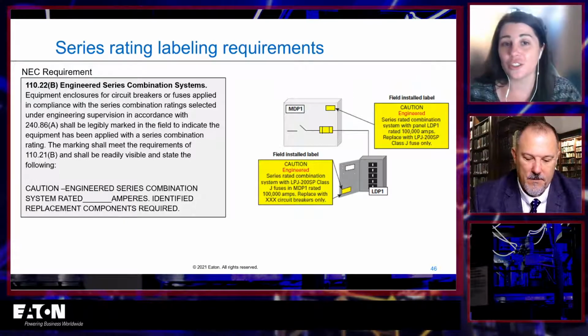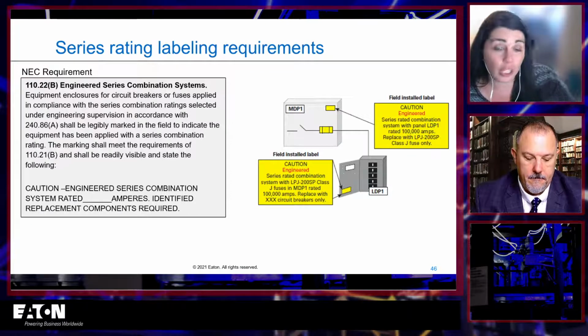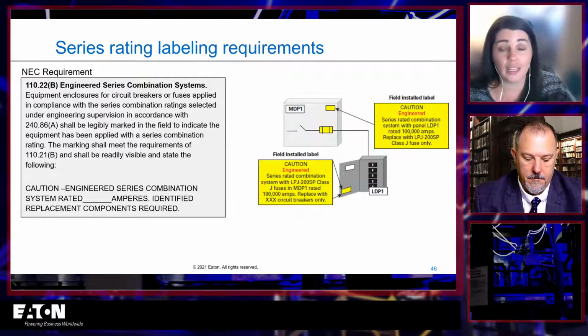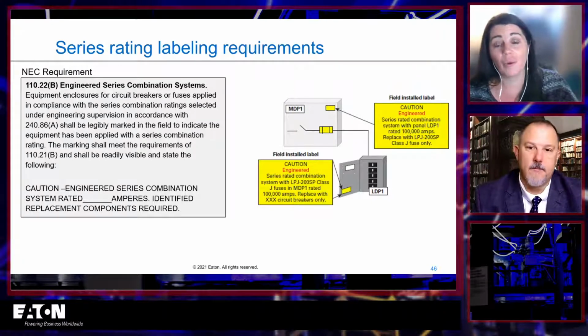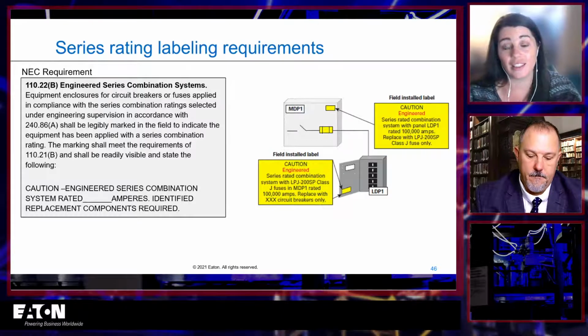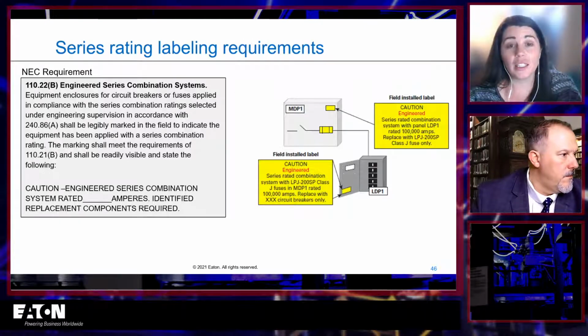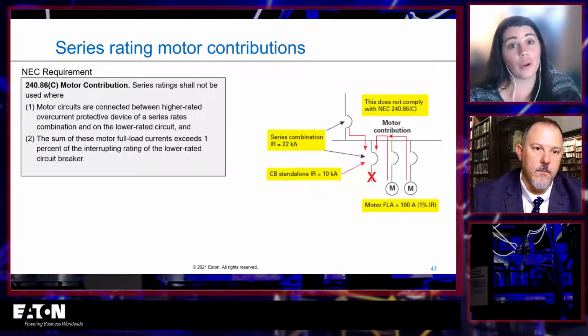Yeah, and there's just additional labeling requirements. Again, this is something I don't want to necessarily read through, but you have to mark both the upstream equipment and the piece of equipment that is being series rated with these caution labels. Caution, this is series rated. Whenever you do any sort of maintenance, you got to be super extra careful. So it's just another thing that you have to do when you have series rating. And then if you go to the next thing, I believe it's motor contributions.